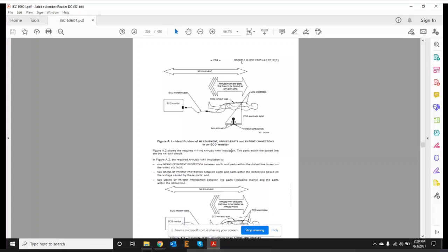Well, let's go to our case study, which is for ECG monitoring. And this should be applicable for the oximeter we had doubt on. So in the IEC 60601-1, you can see they have given one ECG monitoring case wherein the ECG of a patient is to be monitored. So ECG needles, they penetrate inside the body many a times.